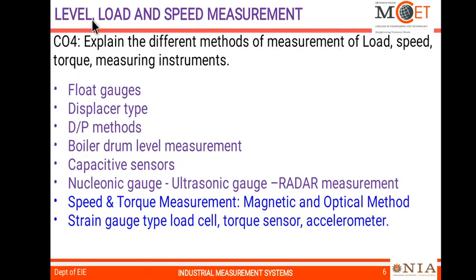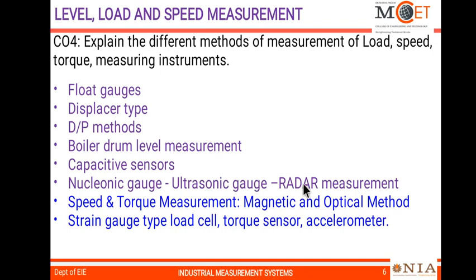CO4 deals with liquid level measurement, load, and speed measurement. For liquid level measurement, float gauges and displacer-type transducers are used for open and closed tanks. The differential pressure transmitter (DPT) method is most commonly used in industries for liquid level measurement, applicable to both open and closed tanks — for example, boiler drum level measurement using DPT. Capacitive sensors are suitable for conducting and non-conducting liquids. Non-contact methods including nucleonic gauges, ultrasonic gauges, and radar measurement are also applicable in process industries.